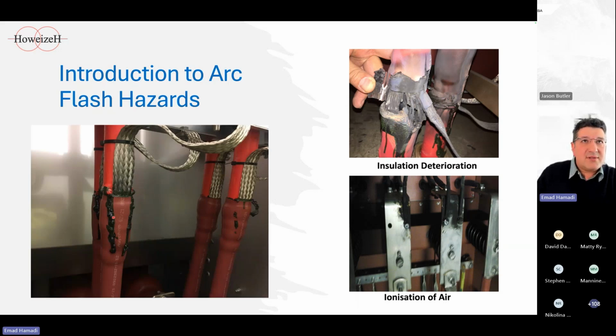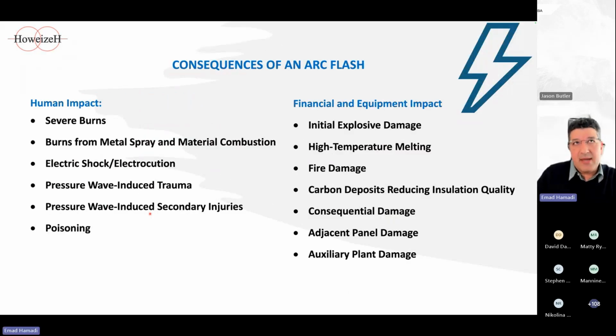And that was the status in the early stages. Actually, this was the other end of this cable, where, as you can see, there is a build-up of heating in the termination of the cable. That could probably be avoided by intrusive maintenance, or, as Jason mentioned, by PD monitoring. But again, these are the consequences of arc flash itself, which David went through, all of them possibly, and I'm not going to repeat them, but as everybody knows, it has human impact and financial and equipment impact.